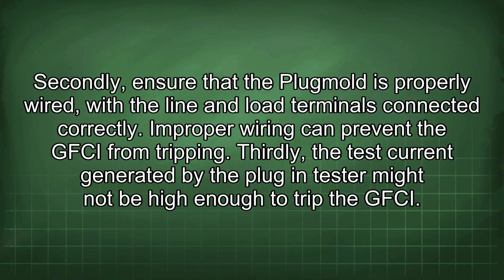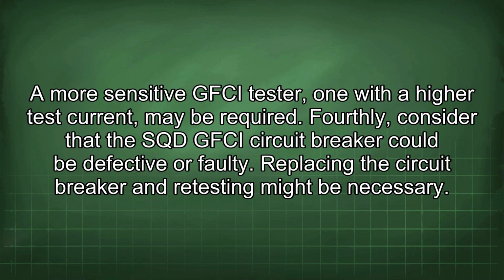Thirdly, the test current generated by the plug-in tester might not be high enough to trip the GFCI. A more sensitive GFCI tester, one with a higher test current, may be required. Fourthly, consider that the SQD GFCI circuit breaker could be defective or faulty. Replacing the circuit breaker and retesting might be necessary.